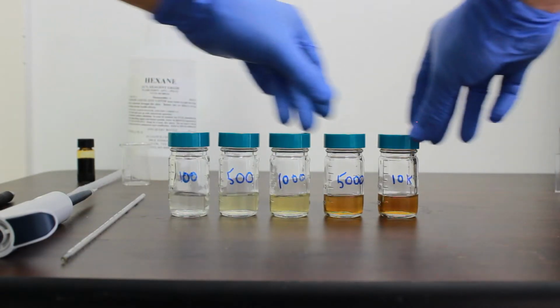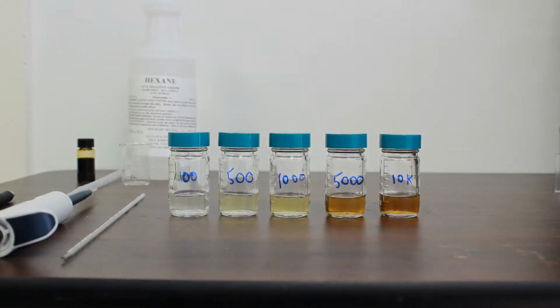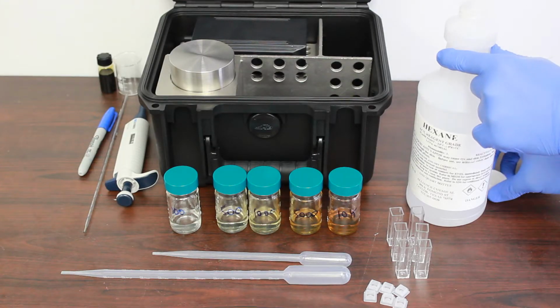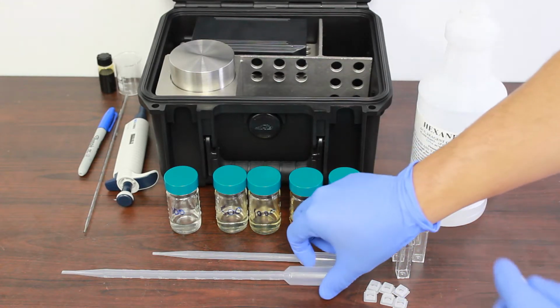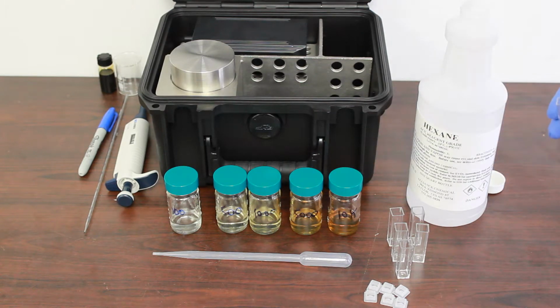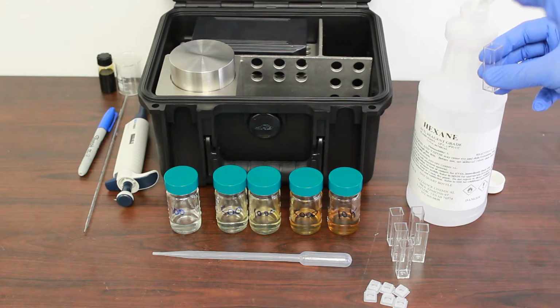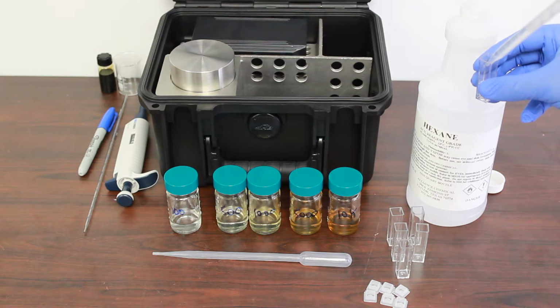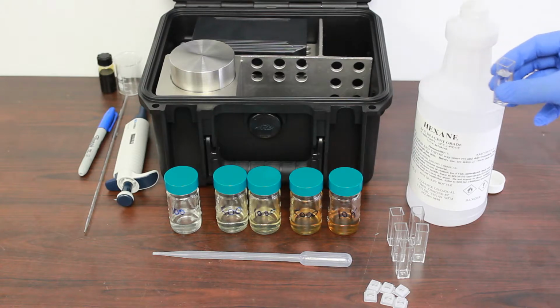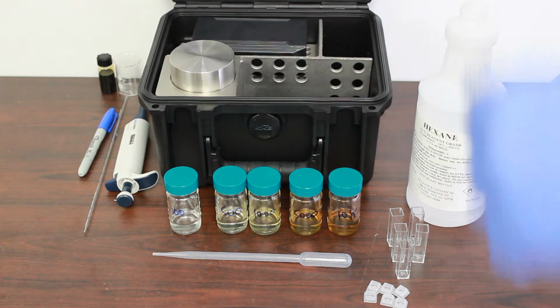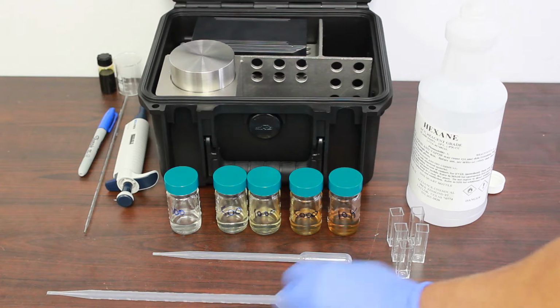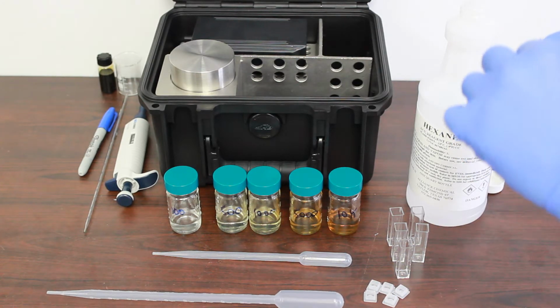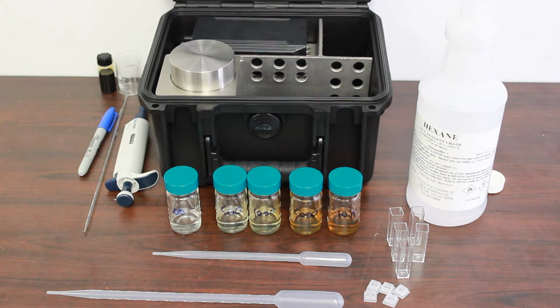With the standards prepared, we can now insert each into the OWB to build the calibration file. The first standard is 0 ppm or pure hexane. The hexane should be inserted into a cuvette and the cuvette inserted into the cuvette cell of OWB. It's sometimes helpful to wipe off the outside of the cuvette if any particulate is seen. It's necessary to cover the cell with the cap before beginning to add the calibration point in OWB.